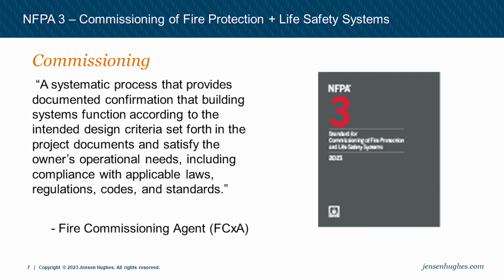So what is NFPA 3? NFPA 3 is the only ANSI-approved commissioning document that deals with fire protection and life safety systems. It's very different—there's similarities, but some distinct nuances between it and more traditional MEP-type commissioning. Here's a definition out of NFPA 3 for commissioning of fire and life safety systems: a systematic process that provides documented confirmation that the building systems function according to the intended design criteria set forth in the project documents and satisfy the owner's operational needs, including compliance with applicable laws, regulations, codes, and standards. That last part is a big difference in what it means to commission a fire and life safety system, and we'll get into that a little bit.